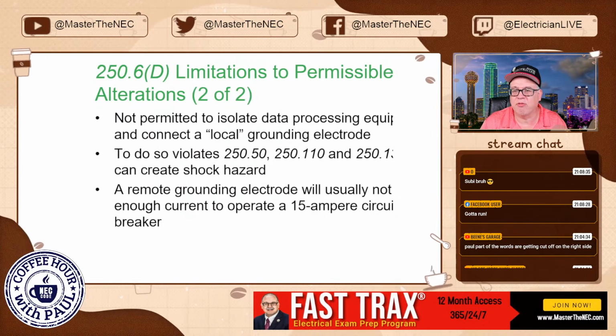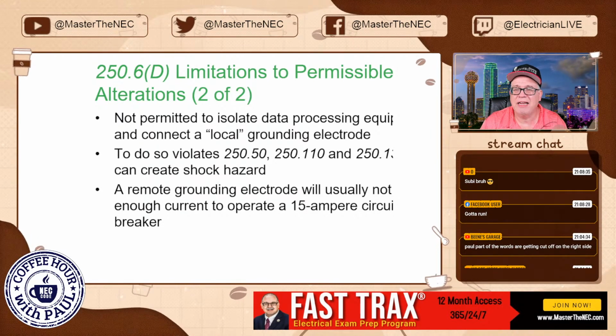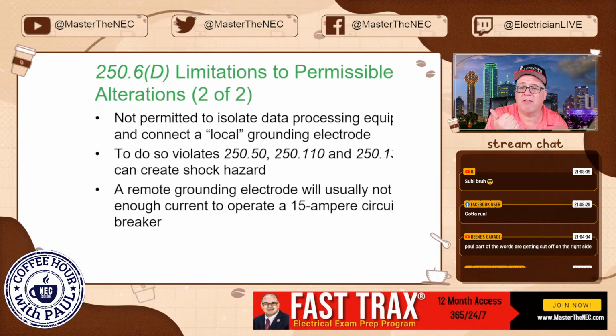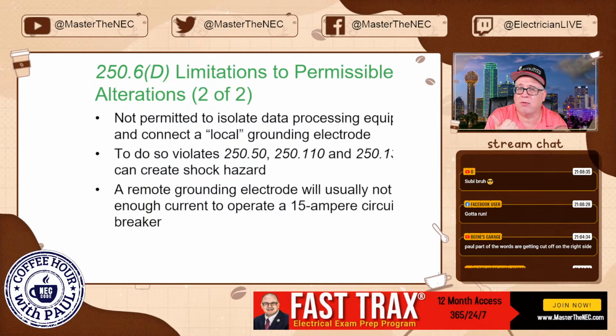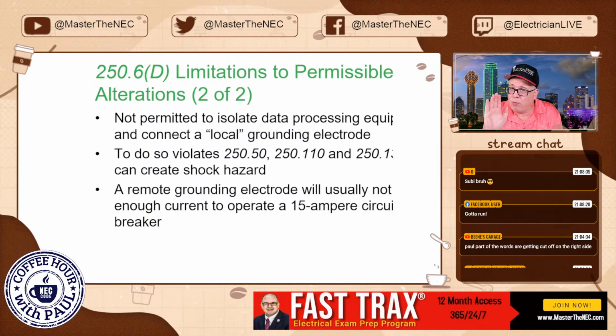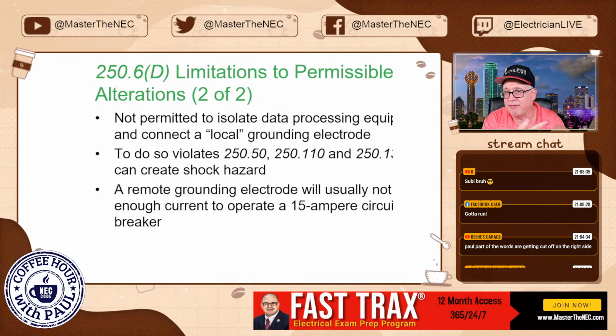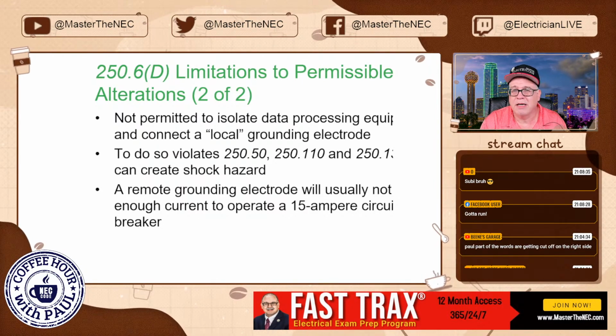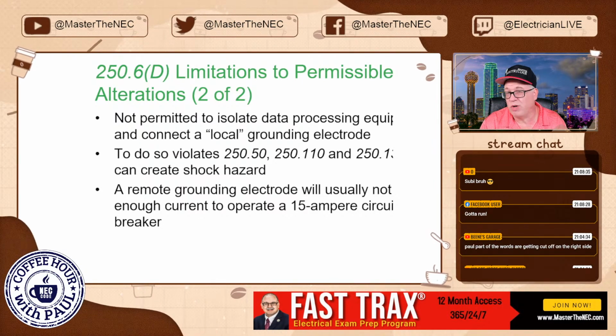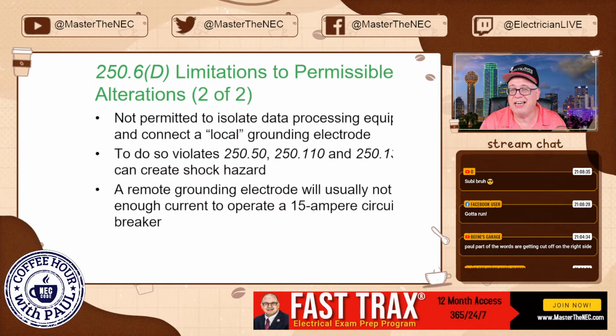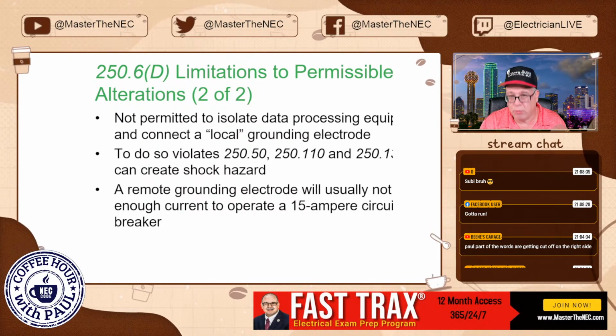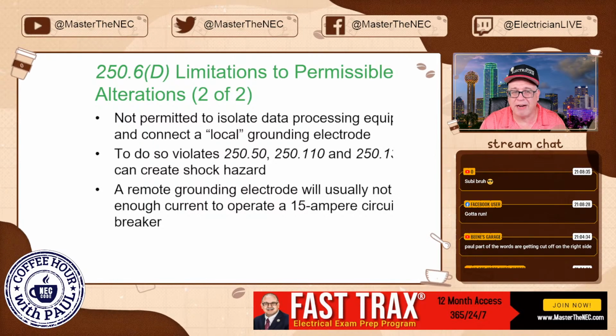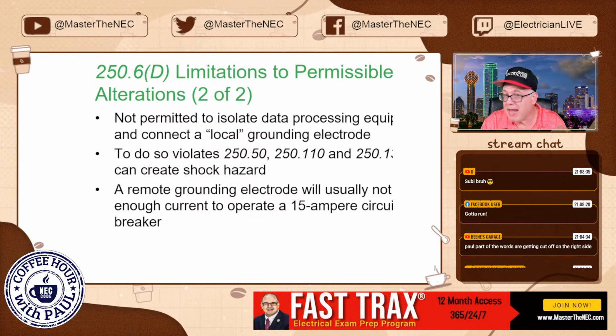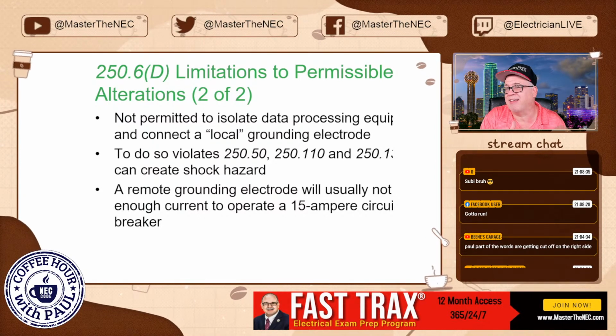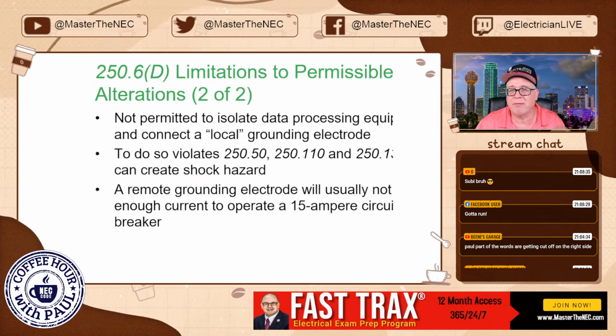About 4.8 amps. Is that going to clear a 15 amp breaker? Absolutely not. So driving your ground rod at your data processing equipment because you want it isolated away from the noise that you might get from the electrical system, not going to happen. So what do you do? You run an individual equipment grounding conductor to it. If you don't want the raceway that may or may not qualify as an equipment ground, you don't want that physically connected to the equipment. So you run something isolated.